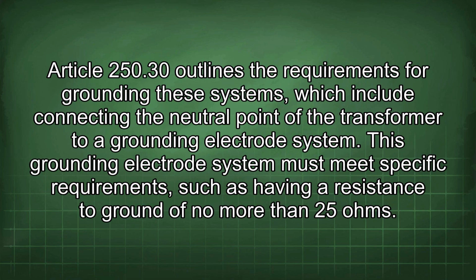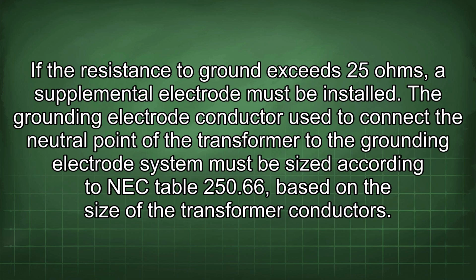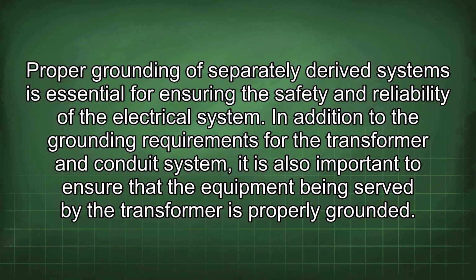Article 250.30 outlines the requirements for grounding these systems, which include connecting the neutral point of the transformer to a grounding electrode system. This grounding electrode system must meet specific requirements, such as having a resistance to ground of no more than 25 ohms. If the resistance to ground exceeds 25 ohms, a supplemental electrode must be installed. The grounding electrode conductor used to connect the neutral point of the transformer to the grounding electrode system must be sized according to NEC Table 250.66 based on the size of the transformer conductors. Proper grounding of separately derived systems is essential for ensuring the safety and reliability of the electrical system.